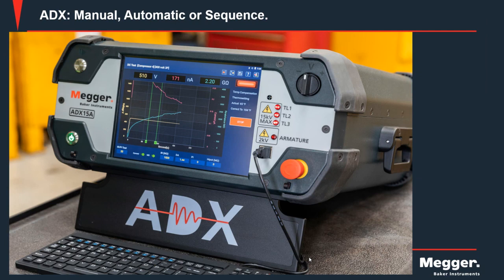It also enables us to trend that result. So if that was a one-off test, we could then test again in 3 months' time, 6 months' time, whatever the sequence of testing of condition monitoring that you wanted to apply would be trended, and we'd be looking for obviously change, because that's what condition monitoring is. We're looking for change in the condition. So this enables us to have a whole different dynamic as per the equipment that used to be used in workshops many, many years ago.